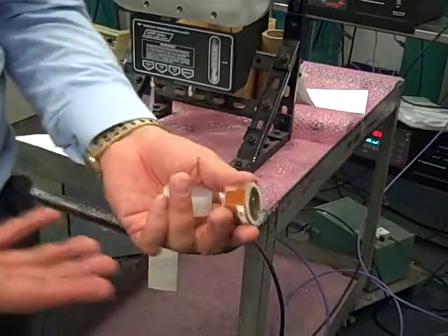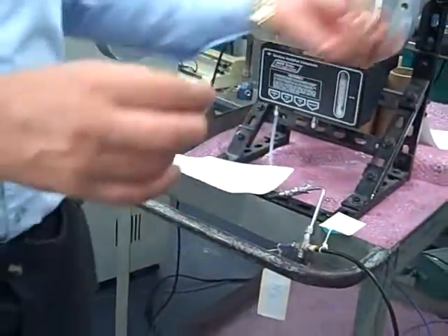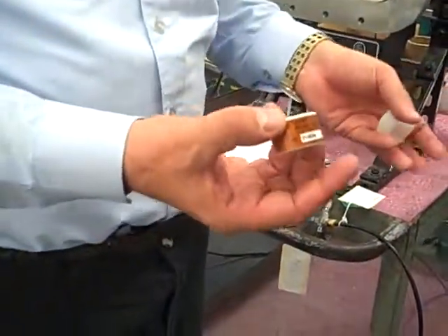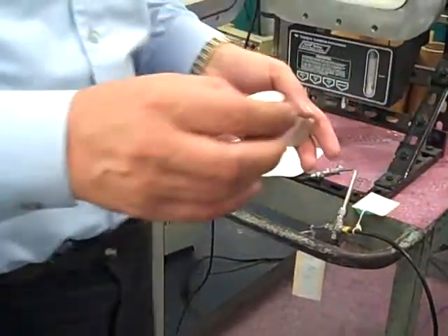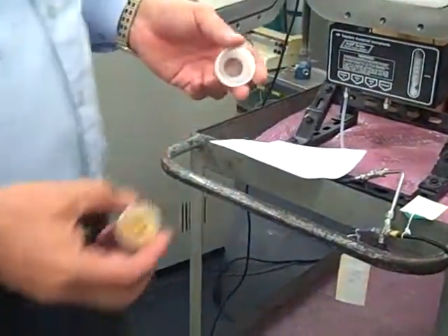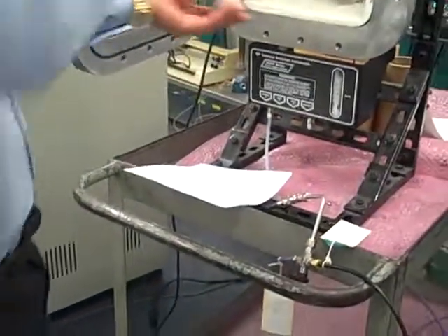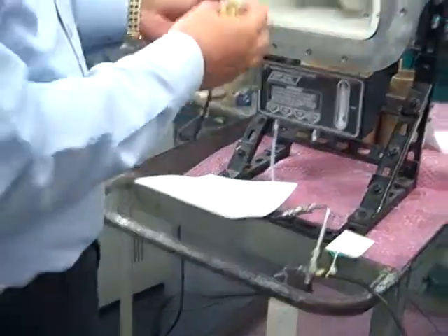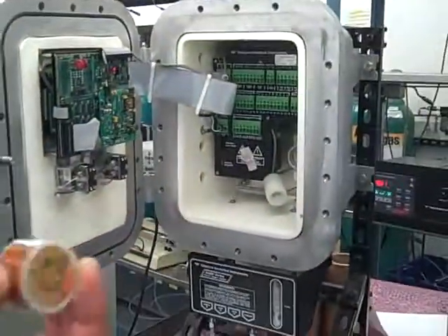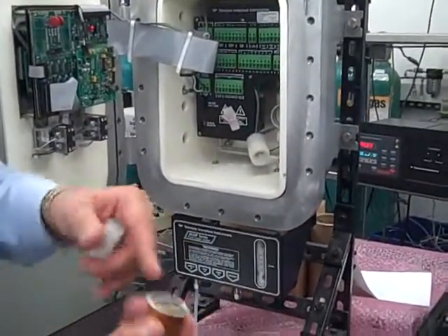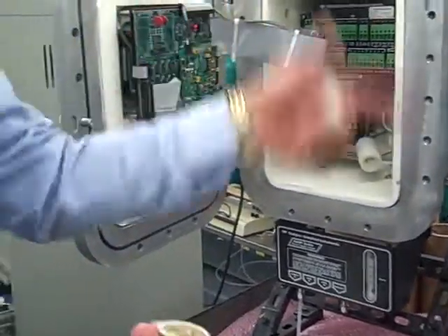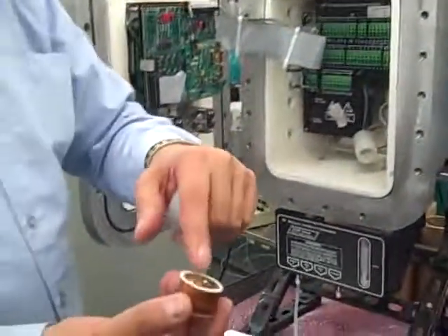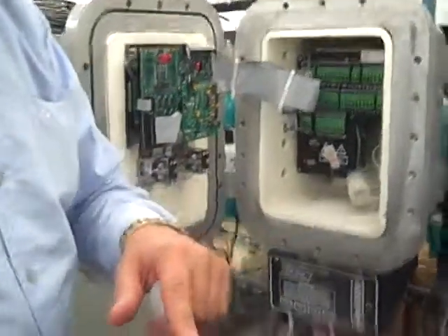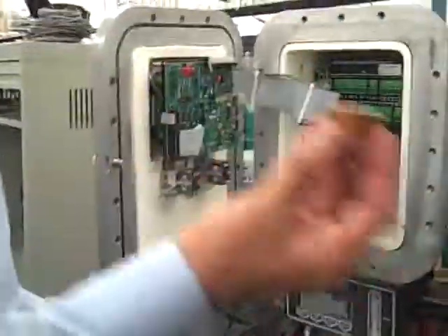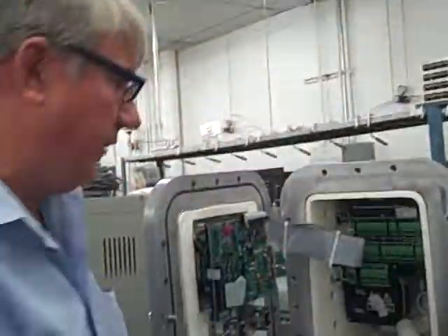Typically, for most Teledyne sensors like this, you should get between 200 to 600 microamps in open air. And that'll tell you if your sensor's good or not. If you have some question, I'm not sure if my unit's bad or my sensor or what's going on, that can tell you in many cases. Now, I should caution you a little bit with a trace oxygen sensor. When it gets a higher output near zero, after 6 months or a year, it'll still put out that 500 microamps of current. So that maybe isn't the best test for that, but certainly for a percent micro fuel cell, it's an excellent test to see if it's still functioning.